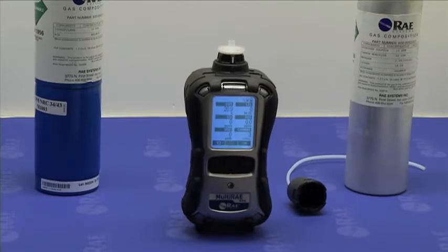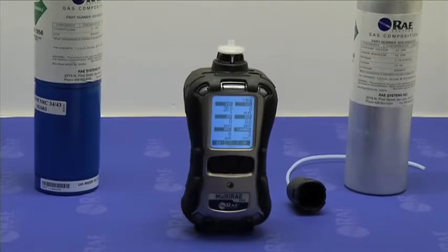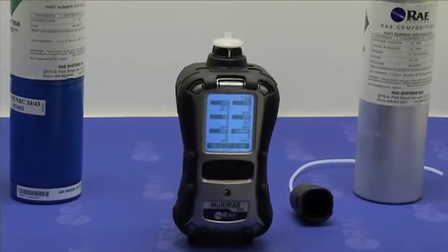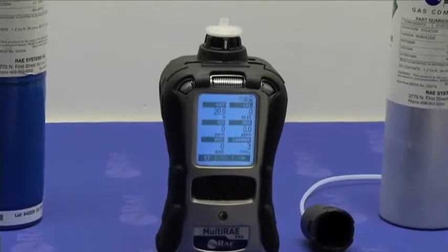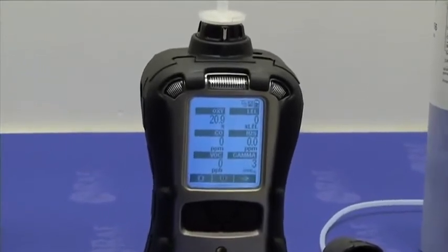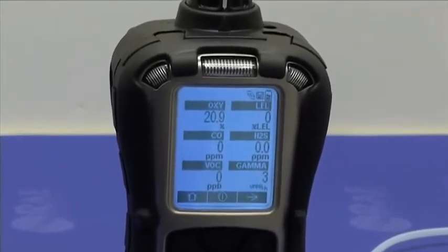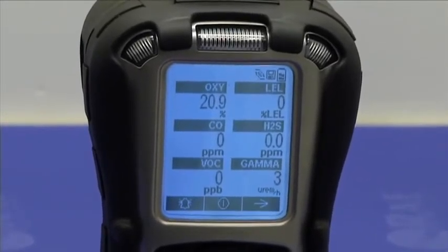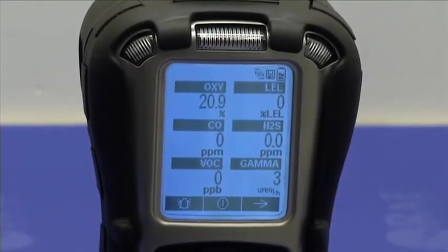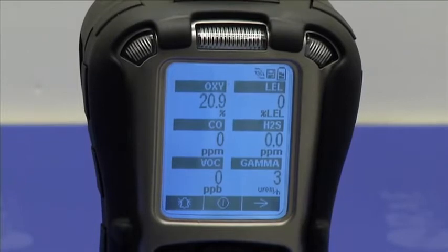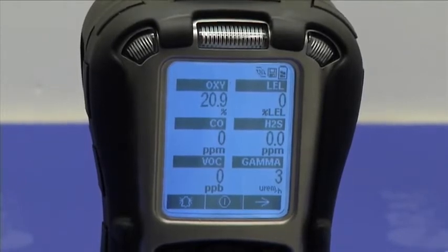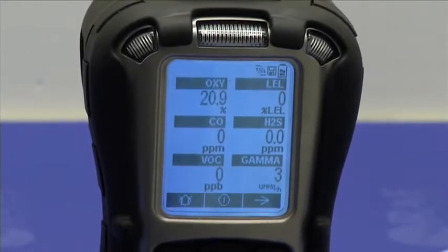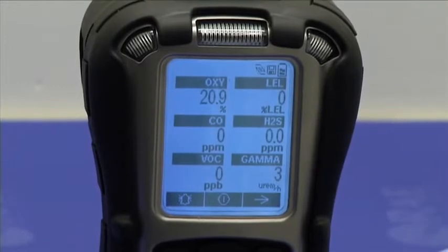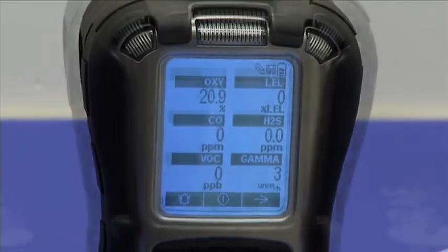The MultiRAE Pro that I have in front of me has a standard configuration that includes the oxygen, LEL, CO, and H2S sensors, the PPB PID, and the gamma radiation sensor. The gamma radiation sensor comes pre-calibrated from the factory and does not require calibration. The other 5 sensors can be calibrated in one multi-sensor span calibration process. Let's review this process in detail.